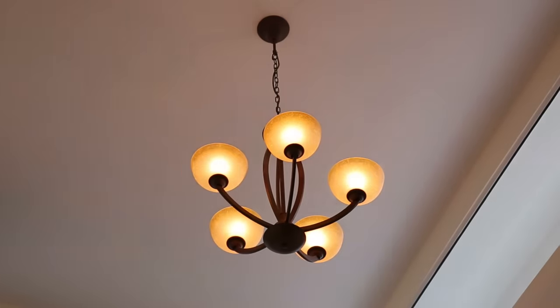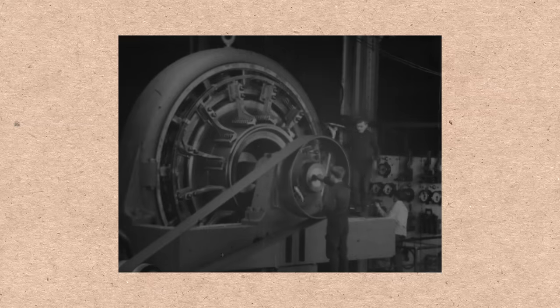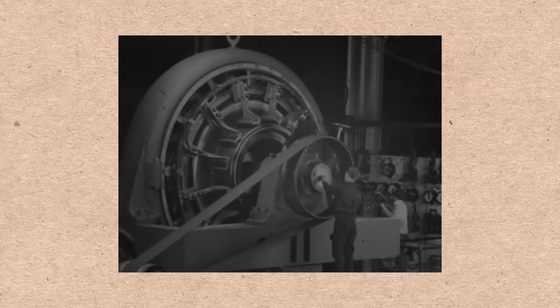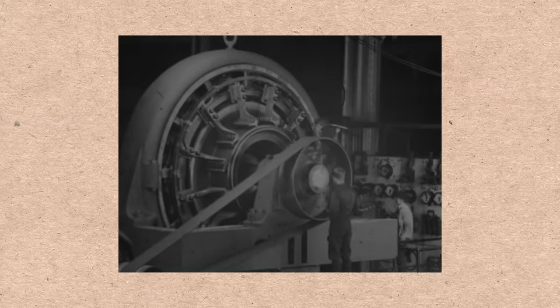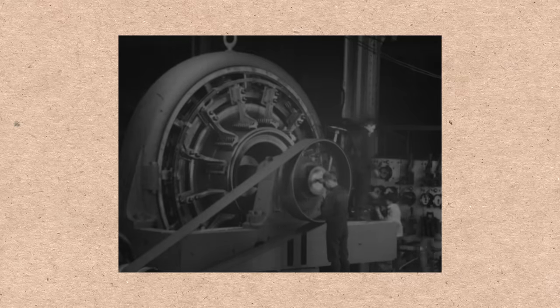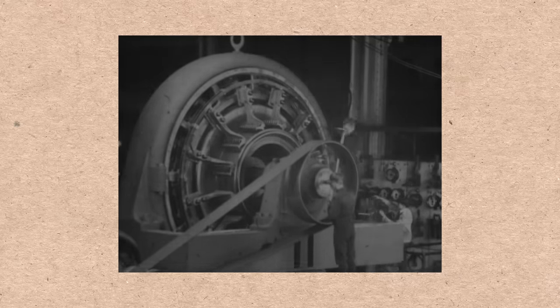Changes in voltage can lead to brownouts or surges that damage connected equipment. One of the benefits of large power grids is electrical inertia. All those huge spinning generators connected together provide momentum that smooths out the ripples and spikes that can occur from equipment faults or quickly changing electrical loads.